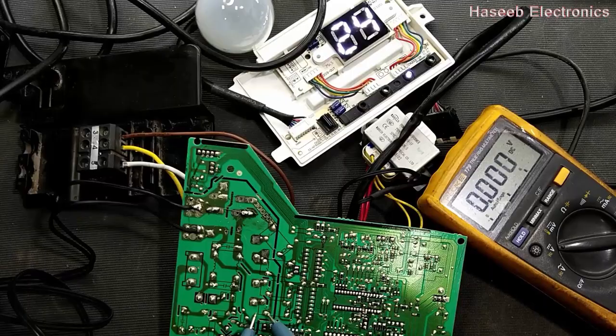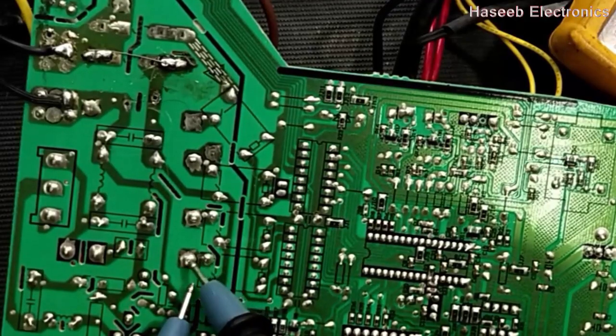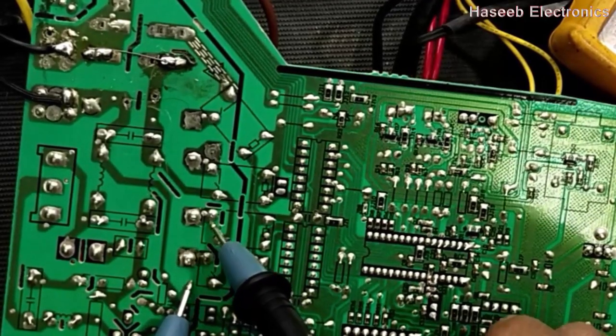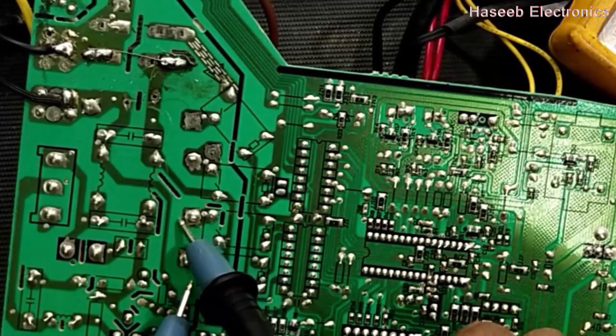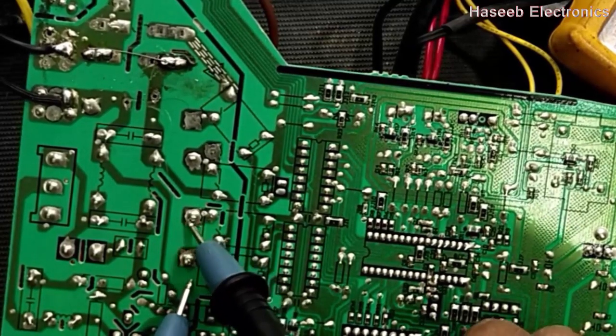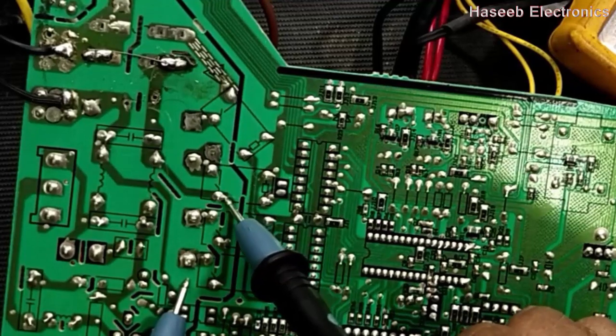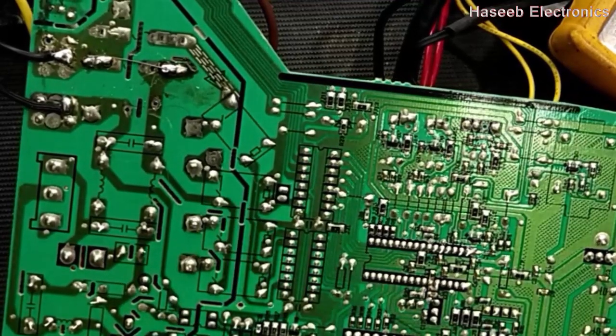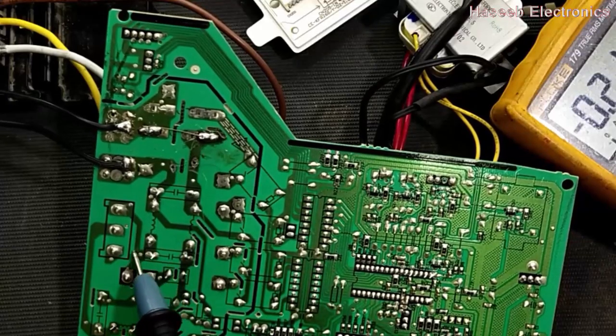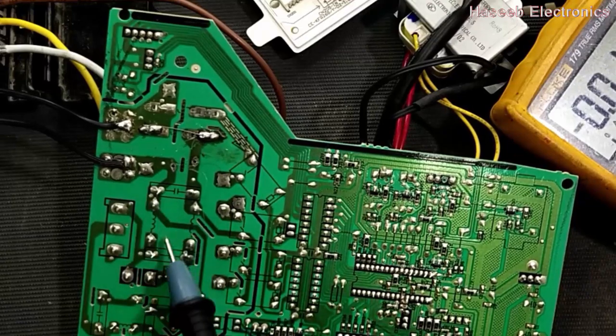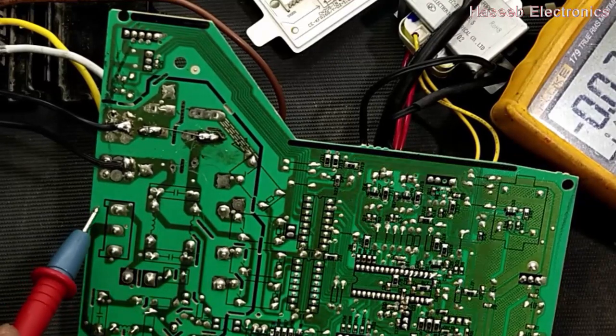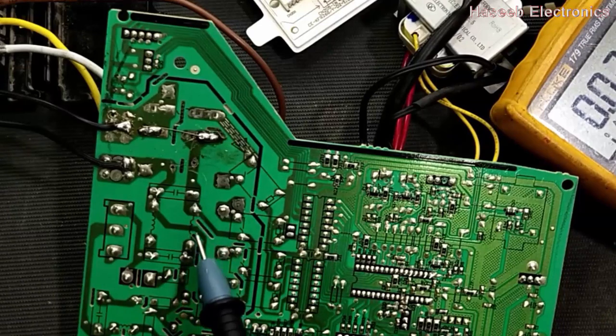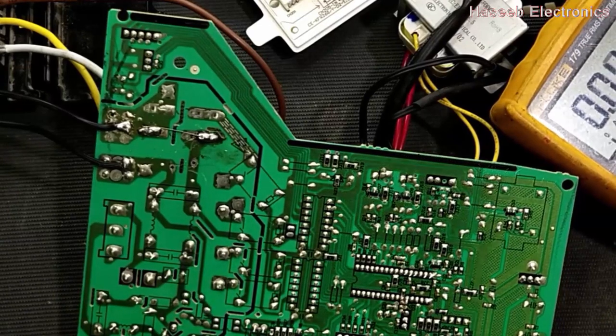If this relay is on, this point will make here, so we will take output. If this relay is on for heat and cool, we will receive voltage here. For the compressor, we will find voltage here. From here, through the filter, the direct neutral line is connected to the indoor blower fan. And these voltages are applied to terminal 1 of the triac.